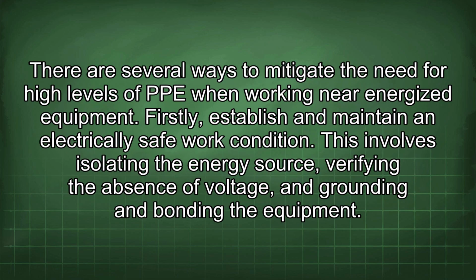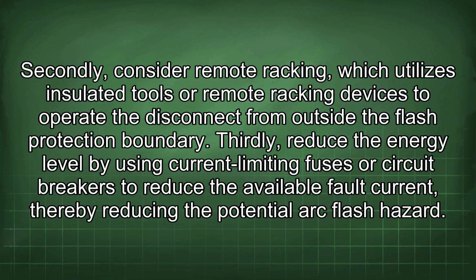There are several ways to mitigate the need for high levels of PPE when working near energized equipment. Firstly, establish and maintain an electrically safe work condition. This involves isolating the energy source, verifying the absence of voltage, and grounding and bonding the equipment. Secondly, consider remote racking, which utilizes insulated tools or remote racking devices to operate the disconnect from outside the flash protection boundary. Thirdly, reduce the energy level by using current-limiting fuses or circuit breakers to reduce the available fault current, thereby reducing the potential arc flash hazard.